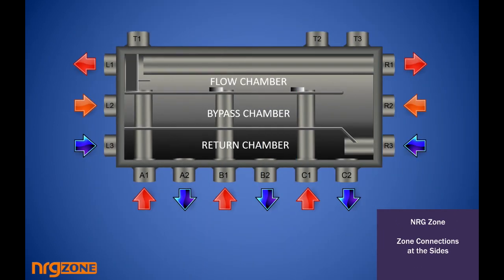Now we have the reverse. We've decided in this scenario we're going to introduce heat into the A1, A2, B1, B2 and C1, C2. So the flow would go in the A1, deliver heat up to the top chamber, and now we're using L1 to take away the heat to, say, let's say hot water or whatever, and we might use R1 to head off maybe through a mixing valve to heating zones.